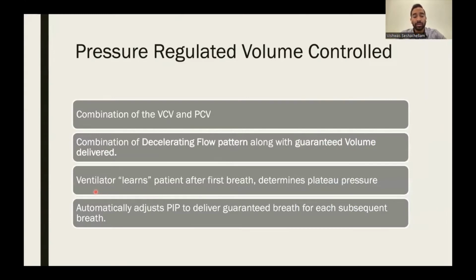So basically what the ventilator does is, after connecting the patient and administering the first breath, the ventilator learns what the patient is doing and determines the plateau pressure. With this plateau pressure, the machine will automatically adjust the peak inspiratory pressure to deliver a guaranteed breath for each subsequent breath. So it's basically volume controlled ventilation, but with the safety of pressure control ventilation.